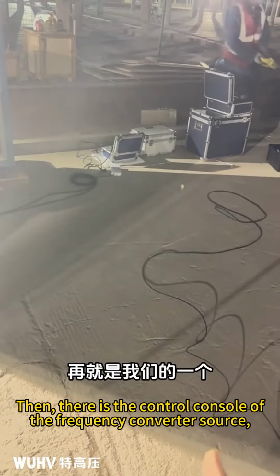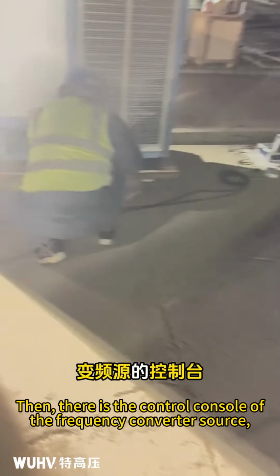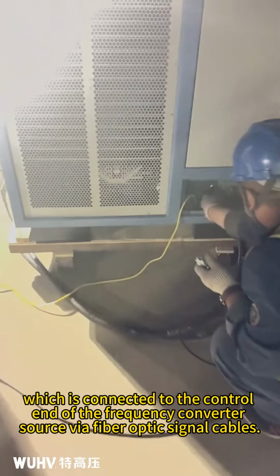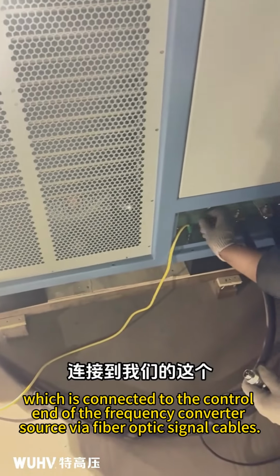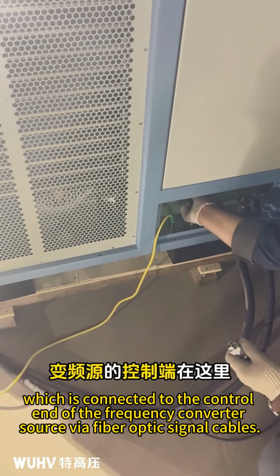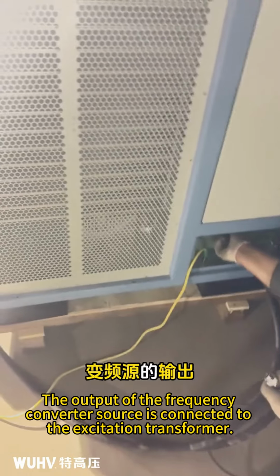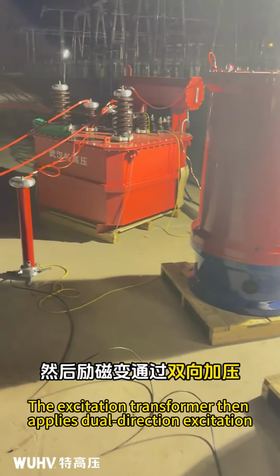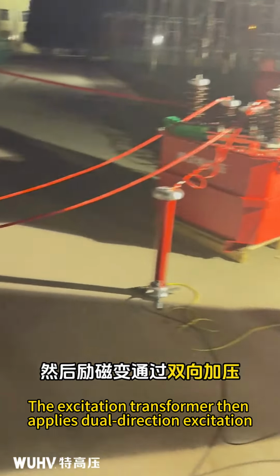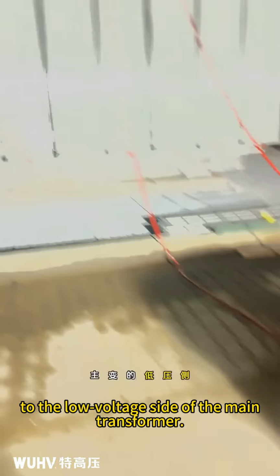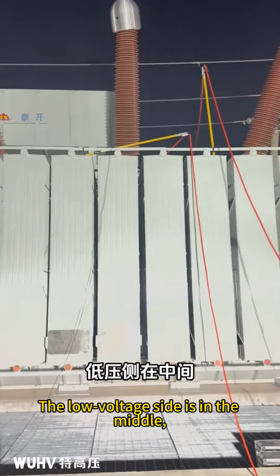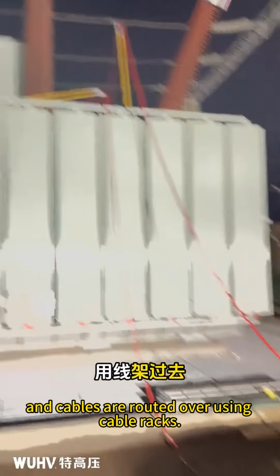Then, there is the control console of the frequency converter source, which is connected to the control end of the frequency converter source via fiber optic signal cables. The output of the frequency converter source is connected to the excitation transformer. The excitation transformer then applies dual direction excitation to the low voltage side of the main transformer. The low voltage side is in the middle, and cables are routed over using cable racks.